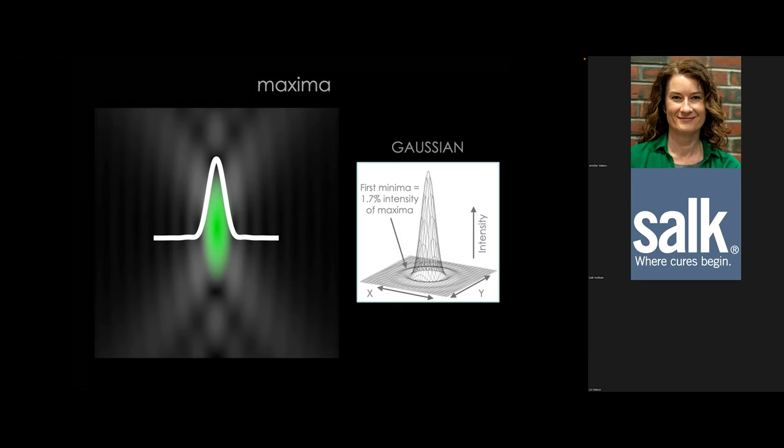Today and tomorrow you'll look at fluorescent microspheres — tiny point sources of light emitting photons — which let us observe the PSF directly. The beads are useful because their size and wavelengths are known, giving us a known ground truth. This reveals what the microscope is actually doing to the image of your biology, unlike a labeled biological specimen where you don't really know the ground truth.